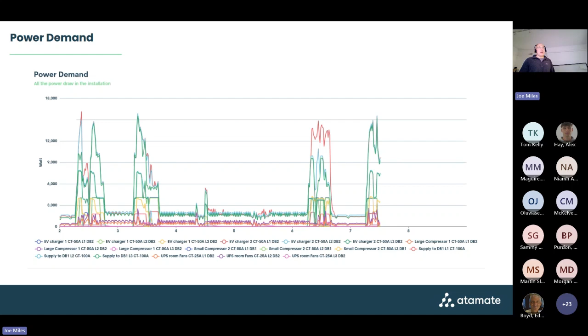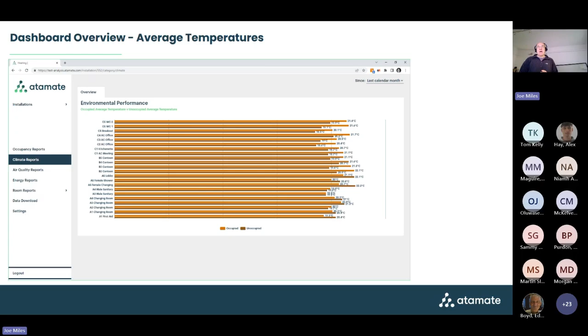We can start looking at the spaces and the temperatures. The top orange line on each room shows the temperature when it's occupied, and the darker brownie line underneath shows the temperature when it's unoccupied. Assuming we're talking about winter here and heating, not aircon, what you want to see is higher temperatures when the space is occupied, and lower temperatures when it's not. That's beginning to show how control systems are or aren't working.